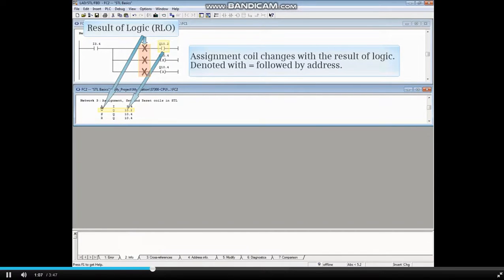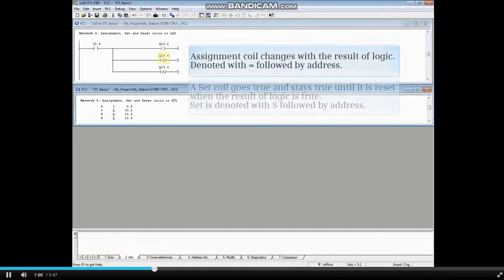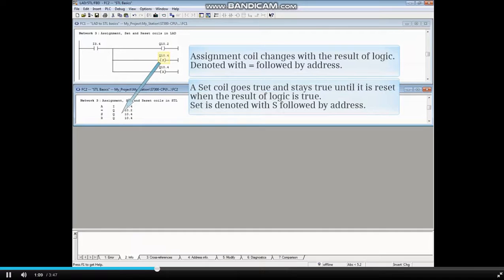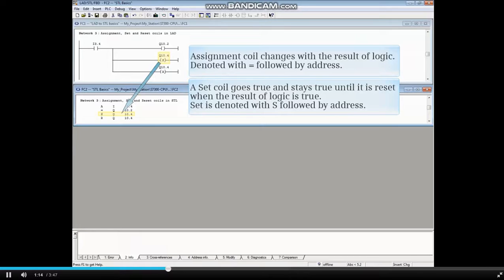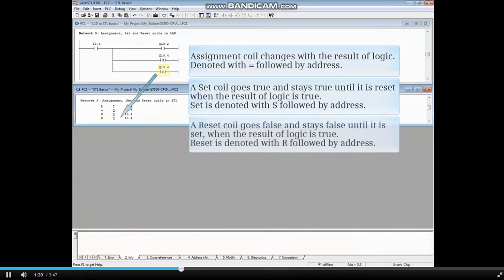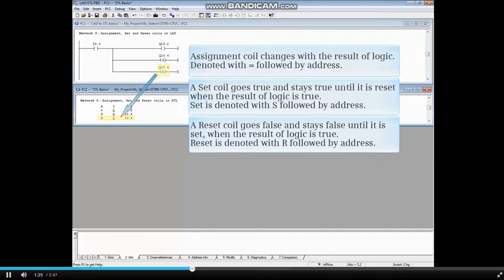It is denoted with equals. A set coil goes TRUE and stays TRUE until it is reset when the result of logic before it is TRUE. Set is denoted with S followed by an address. A reset coil goes FALSE and stays FALSE until it is SET when the result of logic before it is TRUE. Reset is denoted with R followed by an address.